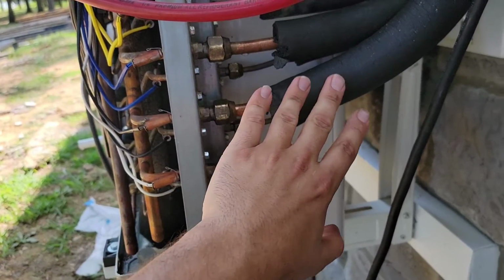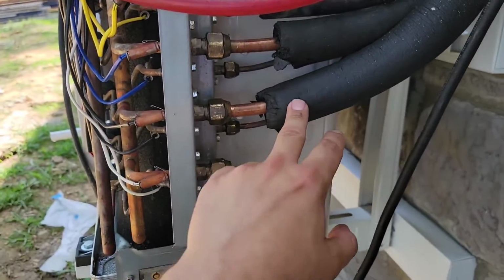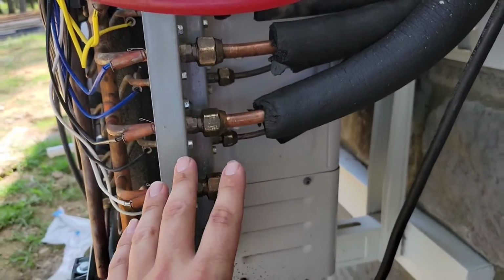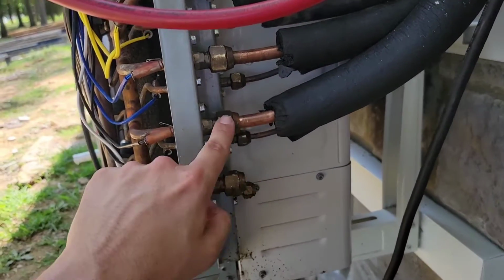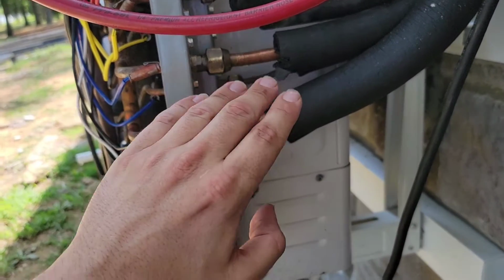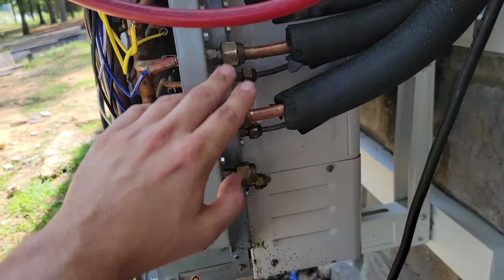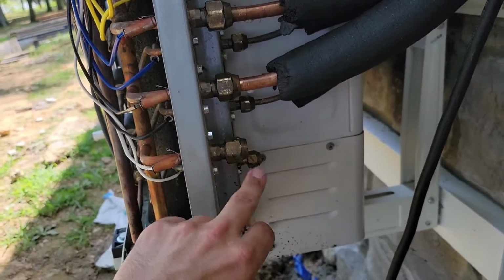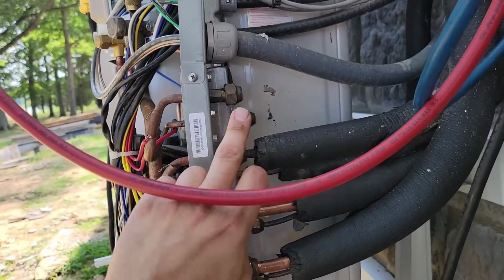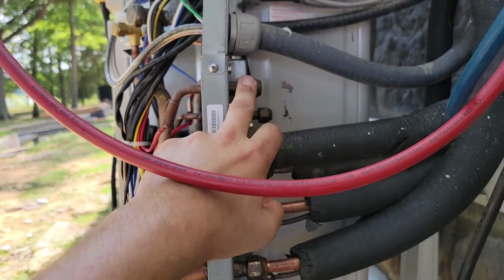Now, my ducted unit is upstairs, and it's my longest line set. So where does it go? Longest line set goes on the bottom. Also, the largest unit goes on the bottom. So if I had another unit and say it was 2 ton, it would go right here. If I had a 9,000 or a 12,000 unit, it would go right here.